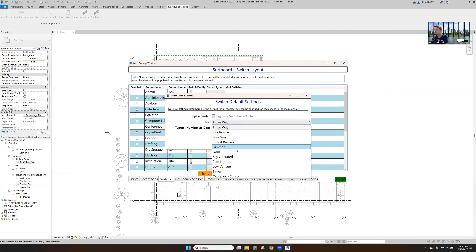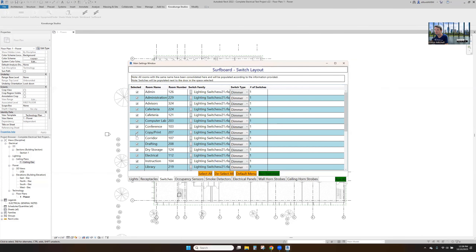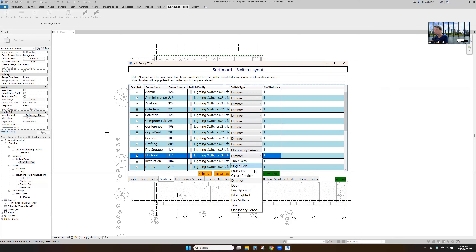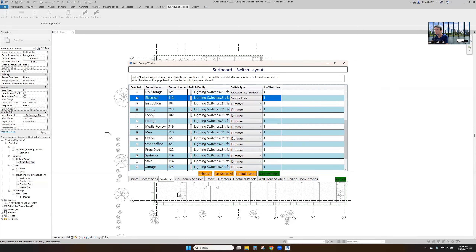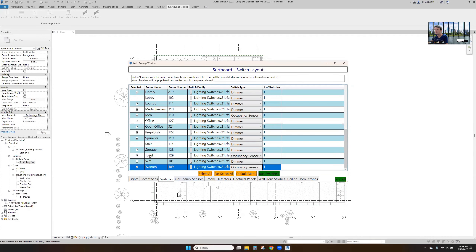That's all our receptacles. Now we've got our switches. We'll start with dimmers, place these typically at the doors. Storage — we want an occupancy sensor in there. A single switch is good in the electrical room. Aux sensor in the men's room, occupancy sensor in the other restrooms, occupancy sensor in storage. Single pole in the sprinkler room.